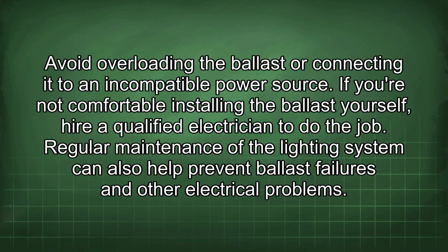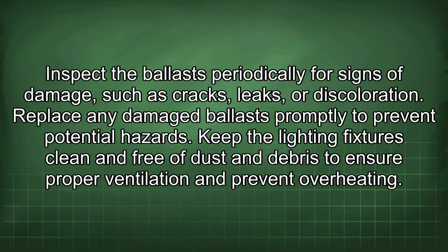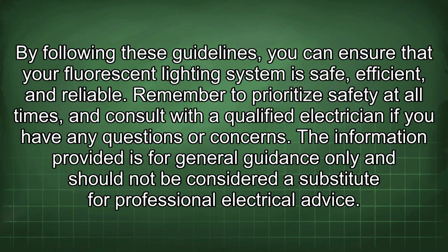Regular maintenance of the lighting system can also help prevent ballast failures and other electrical problems. Inspect the ballast periodically for signs of damage such as cracks, leaks, or discoloration. Replace any damaged ballast promptly to prevent potential hazards. Keep the lighting fixtures clean and free of dust and debris to ensure proper ventilation and prevent overheating. By following these guidelines, you can ensure that your fluorescent lighting system is safe, efficient, and reliable.